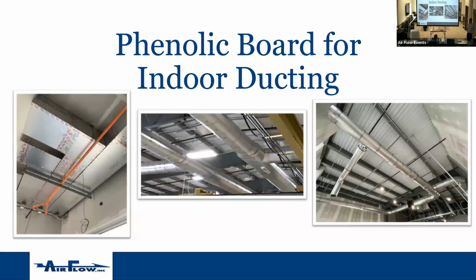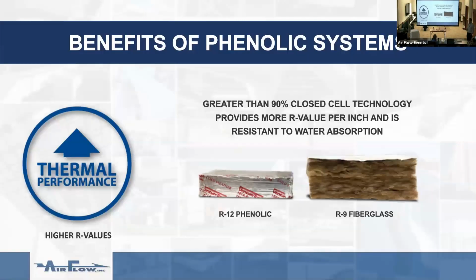Okay, so this is the indoor product. We saw Koolduct examples in the first section. They also make round, they also make oval, it's cool stuff. When we use R8 fiberglass versus R12 phenolic, we see there is a space advantage. With R8 fiberglass, typical indoor insulation, we can't squeeze it and keep R8. It's got to be loose, right? But sometimes we're in tight spaces and we have to band it, so this insulation loses some of its value when it collapses. R12, you can stand on it, it doesn't collapse. It is rigid.